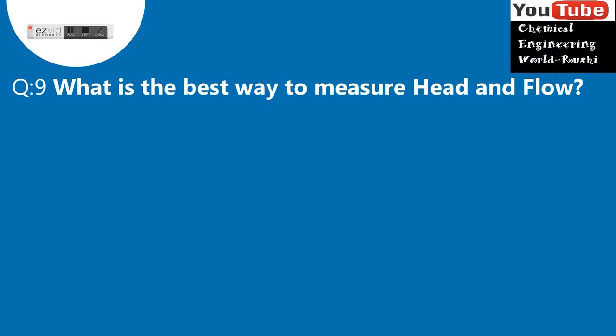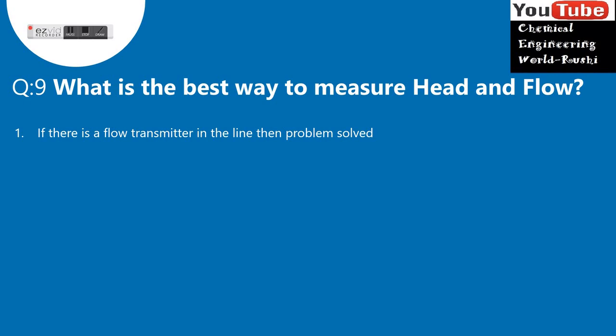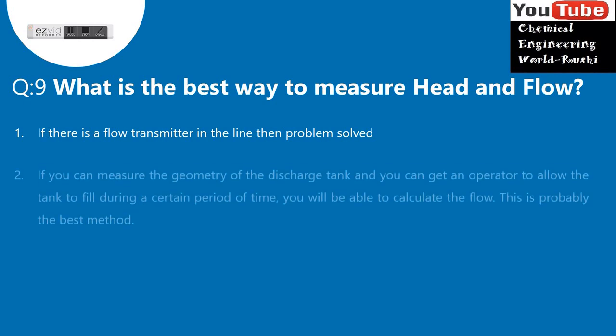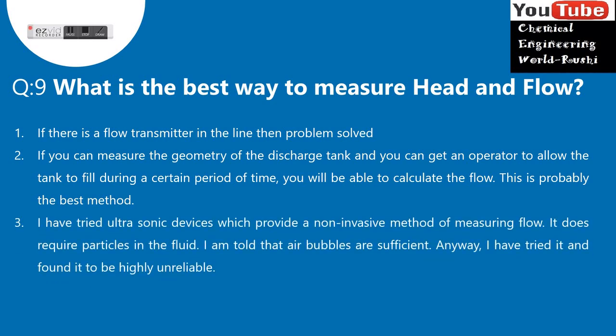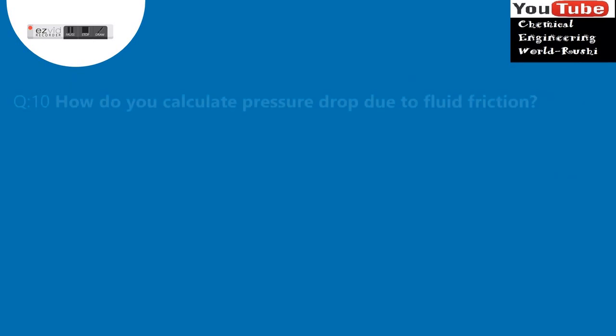Question 9: What is the best way to measure head and flow? 1. If there is a flow transmitter in the line, then problem solved. 2. If you can measure the geometry of the discharge tank and get an operator to allow the tank to fill during a certain period of time, you will be able to calculate the flow. This is probably the best method. 3. I have tried ultrasonic devices which provide a non-invasive method of measuring flow. It does require particles in the fluid — I am told that air bubbles are sufficient. However, I have tried it and found it to be highly unreliable.